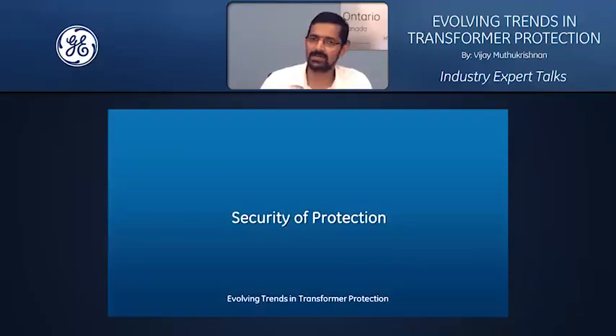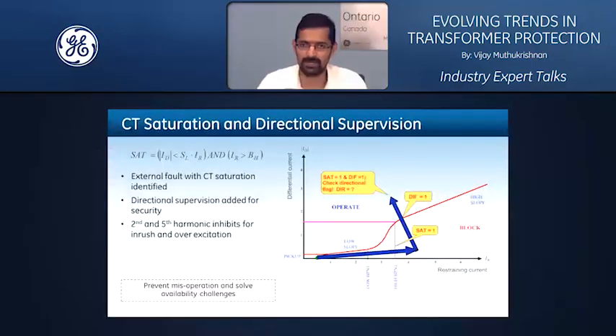Now, moving on to the next dimension, security of protection. I mentioned that security is nothing but the stability of transformer protection for through faults or external faults. Now, we have the dual slope, dual breakpoint characteristic. You can use the second slope to a certain extent to achieve through fault stability. However, technology innovation is further advancing, and applying principles like CT saturation detection and directional supervision really enhances and takes the stability for through faults to the next level.